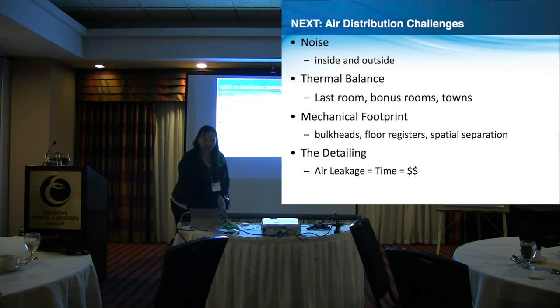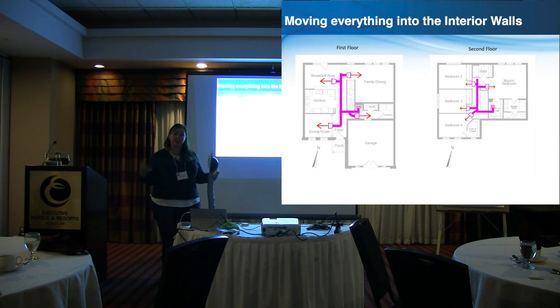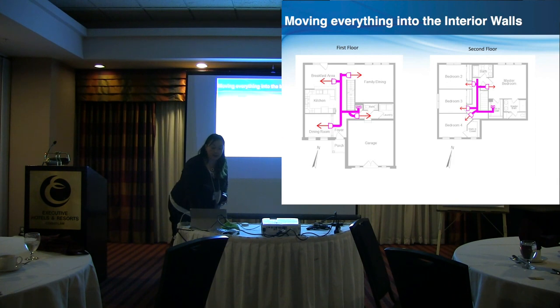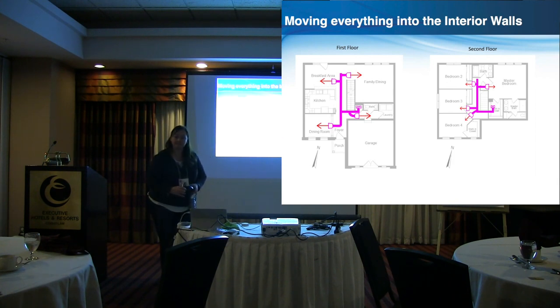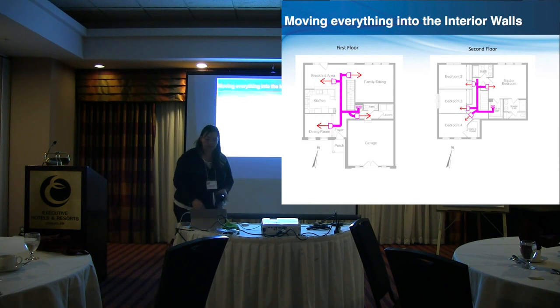And then on the contractor side, more importantly, think about anyone can use modulation, get the traditional ducts down at 10% leakage. Guys, how much extra time is that to get from what you're doing now to consistent 10% leakage? Extra couple of hours? So that's your time. So how can we help you speed up that installation time to get consistent under 10% leakage? All right, so we bring everything into the interior walls of the house, 6-inch or 8-inch mains, and we put everything 6 inches from the ceiling, and we let science take over.